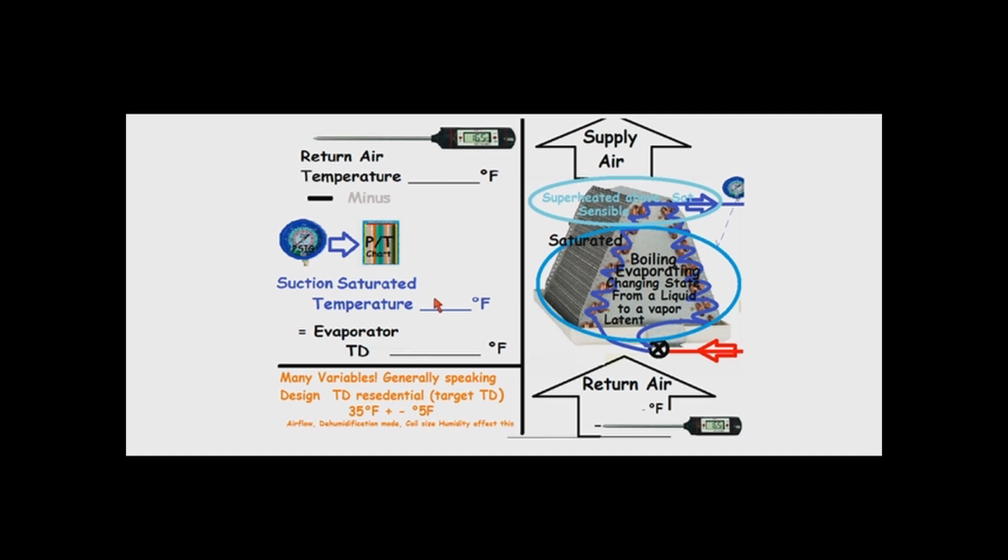That means as the air temperature coming into this evaporator coil dropped, my suction pressure and saturated temperature also dropped. And once we get to 32, it's going to start to freeze. Depending on the amount of moisture in the air, it will start to freeze up. Now there are several things that affect that. That's going to be the humidity, the outdoor temperature, the amount of airflow going across that, the filter, the duct system, if the duct system is perfect, how dirty that evaporator coil is. There's a lot of factors that affect when it starts to freeze. I typically start seeing evaporators starting to freeze at 68, 69 degrees because no duct system is perfect. They're usually restricted.